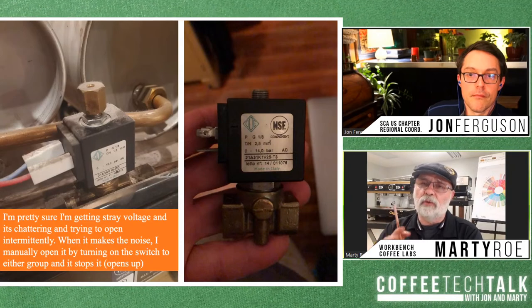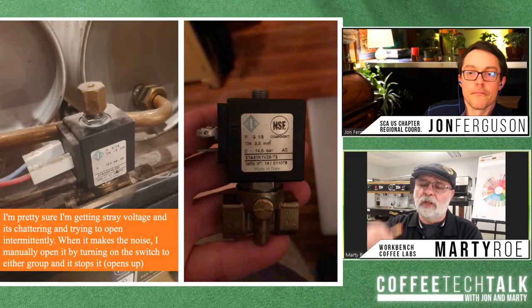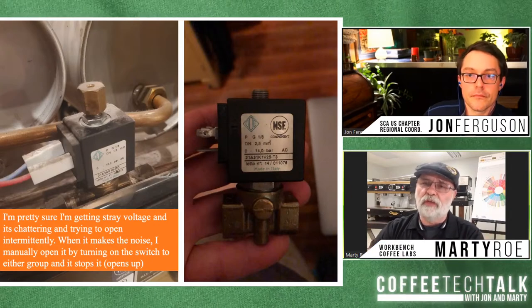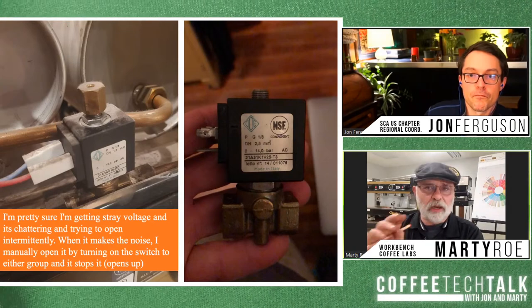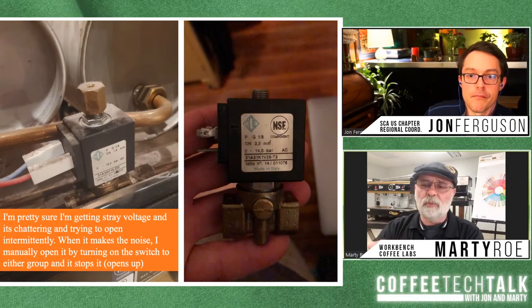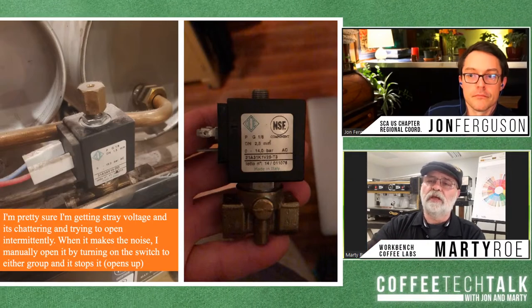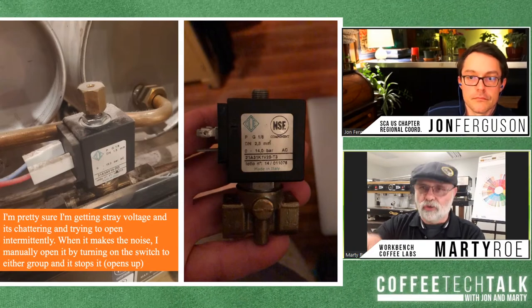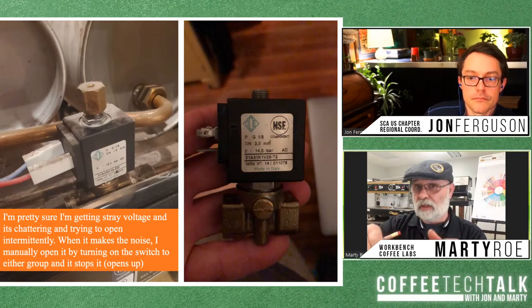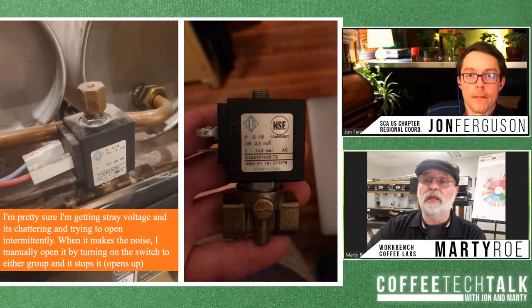With that being said, if they're put in physically correct, when that plunger comes up and water is rushing down past that plunger, you need to be feeding the coil whatever voltage it's rated at to lift that securely up out of that hole, because the water rushing down is going to want to drag, kind of a Venturi effect. It's going to want to drag that plunger down, and it causes it to chatter when it does that.